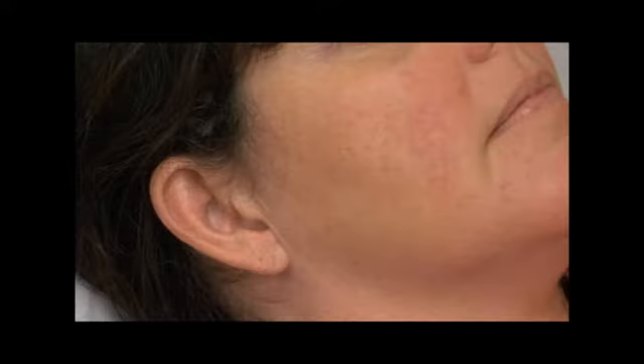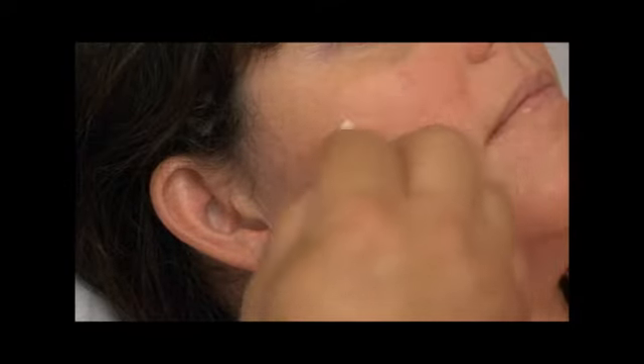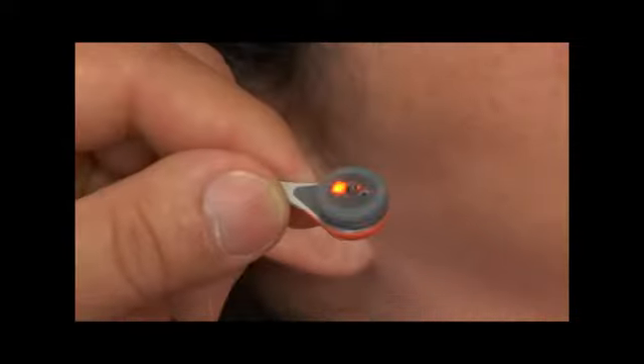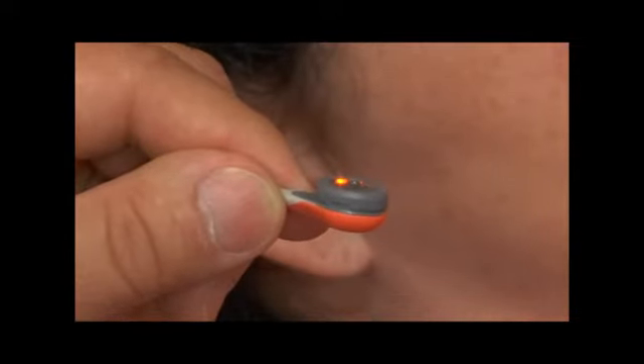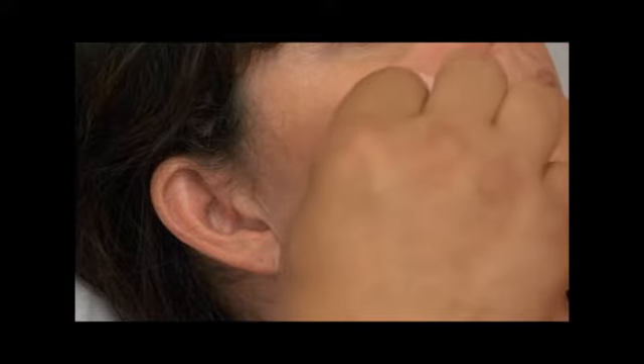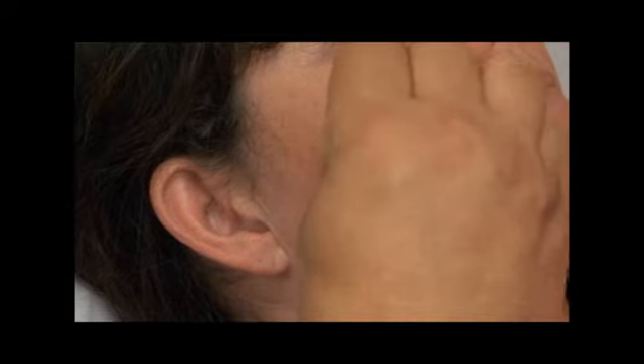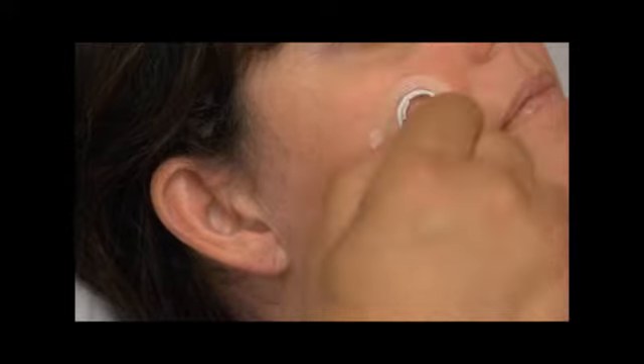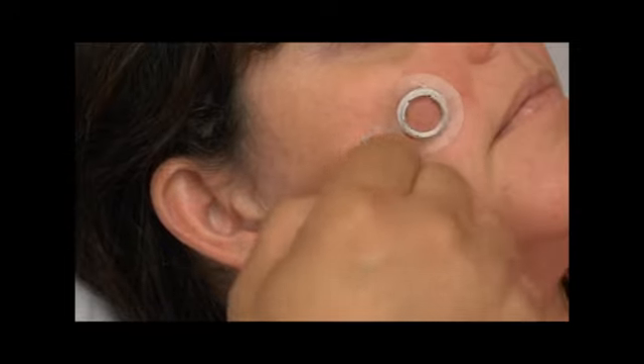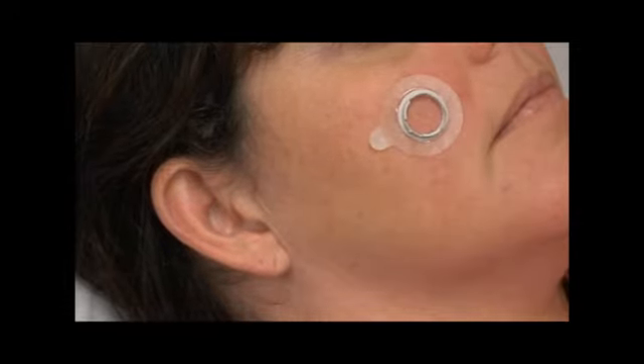Multi-site attachment rings. Clean the skin with alcohol where the multi-site ring is to be used. Reapply 1 small drop of Sentec contact gel or water to the sensor membrane. Remove cover of adhesive tape of the attachment ring and attach the ring to the measuring site. Move your finger around the ring circumference to ensure a good adhesion of the entire adhesive to the skin.